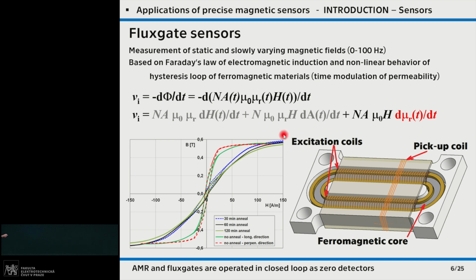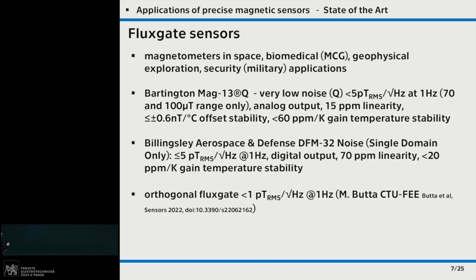So we can see that there is some change of the flux within the cross section of the coil, of the pickup coil - that's basically how the sensor works. On the pickup coil we get a second harmonic voltage, which is then directly proportional to the measured field. Why am I talking about that? Because the magnetic core properties basically define the most important properties like the noise and the offset stability and so on. So one has to be very careful when designing it, operating it, embedding it, and so on.